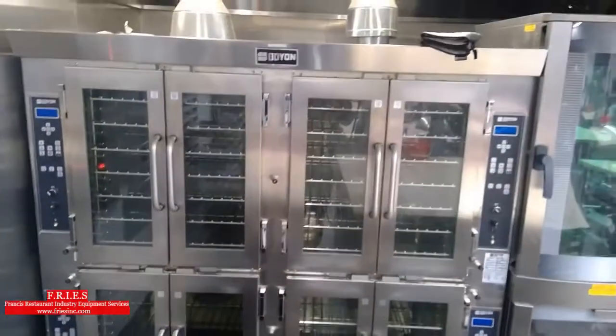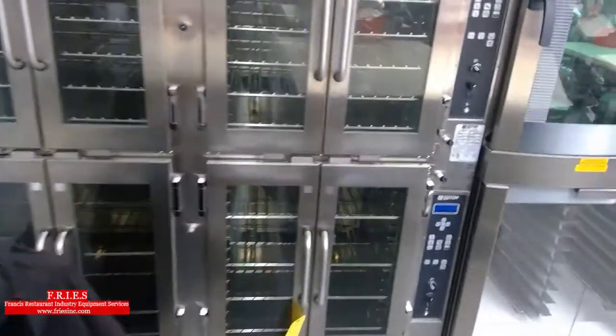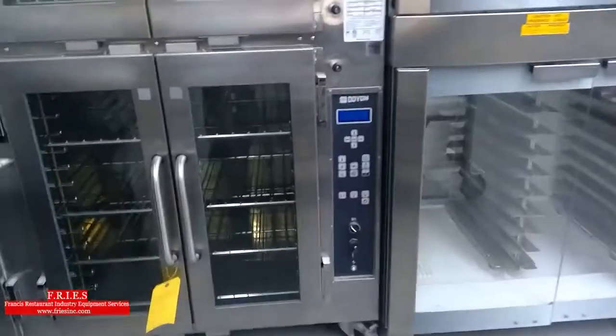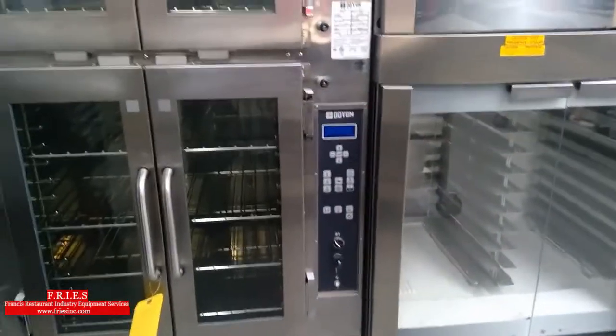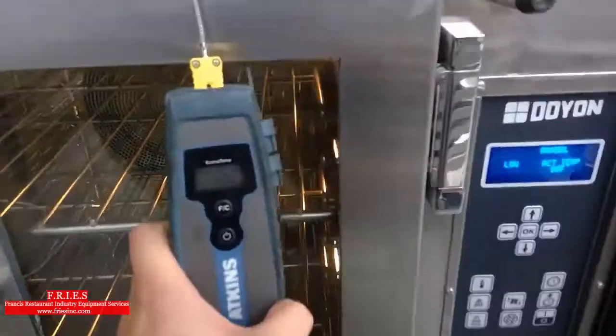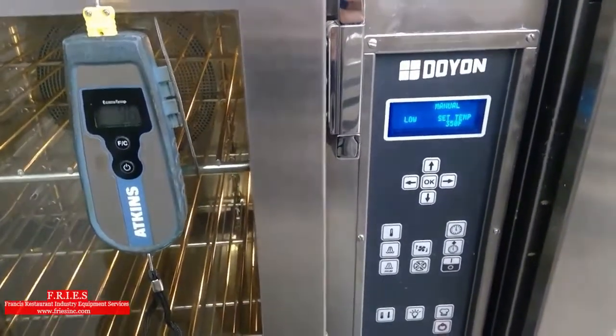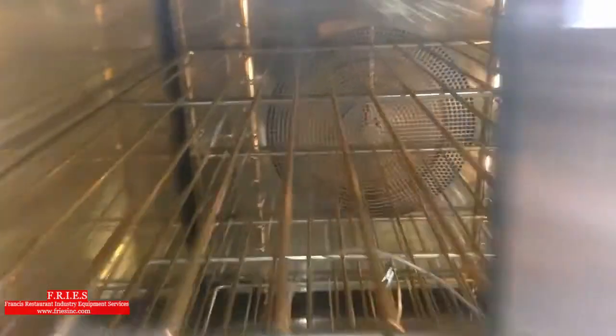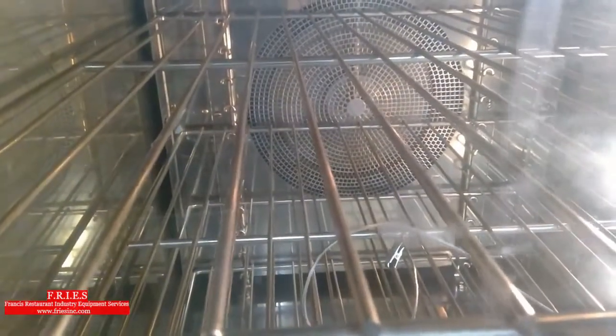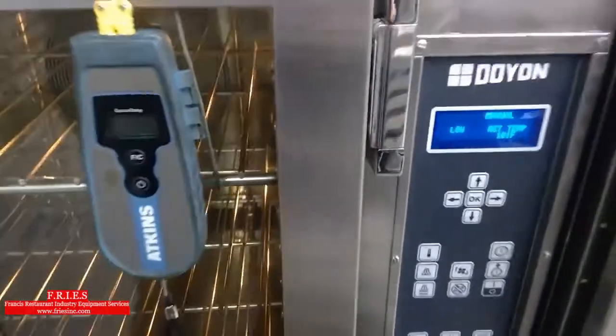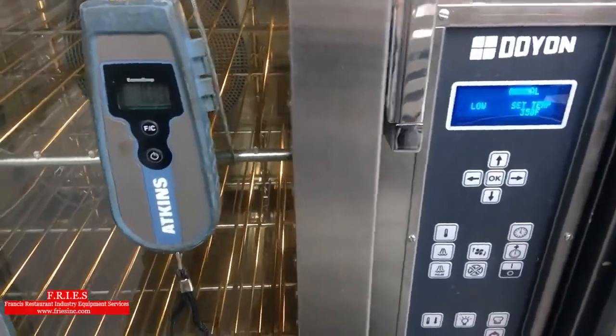Alright, I have a Doyon bakery convection oven that's not getting hot enough. So this beast here, it's the bottom right hand oven that's not getting hot enough for them. So I'm just going to fire up the unit here. Blower motor's running, I'm just doing the basic checks. Temperature's going up, so the burner is on.